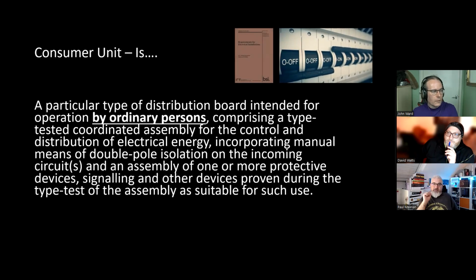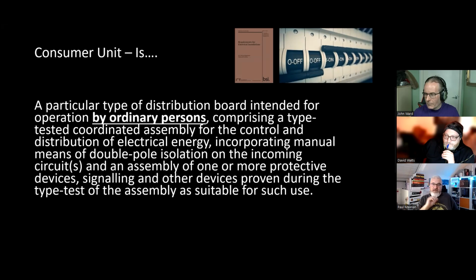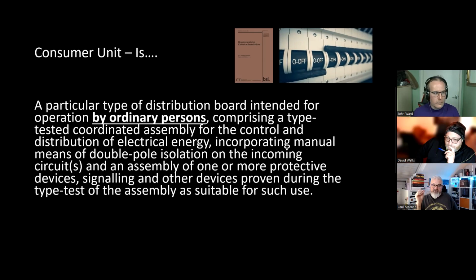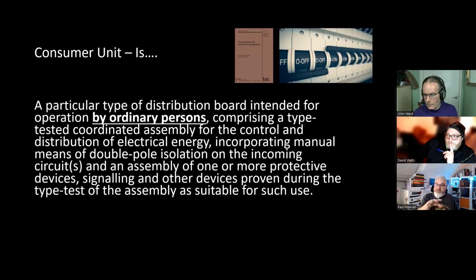So it's now, under the Brown Book, a particular type of distribution board intended for operation by ordinary persons. So it's considering the utilization side of it. Operation by ordinary persons, would you let someone near rewirable fuses? Are they instructed? Who knows? Comprising a type-tested coordinated assembly for the control and distribution of energy, incorporating manual means of double pole isolation on the incoming circuit, and assembly of one or more protective devices, signaling and other devices proven during the type test assembly. So they keep banging on about type tests, but they've removed fuses. So I'm taking this as our fuse boards, as in old-fashioned fuse boards and rewirables, now not defined as a consumer unit anymore, and hence are they compliant?